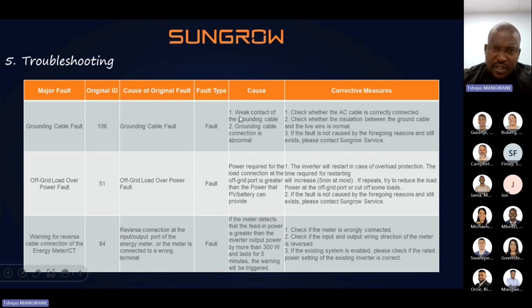What is the cause of it? It could be that there's a weak contact of the grounding cable. Second, the grounding cable connection is abnormal. Okay, what are the corrective measures to resolve this issue? The first one, they said, check whether the AC cable is connected correctly. Okay. Secondly, check whether the insulation between the ground cable and the live wire is normal. You don't need that side on site.